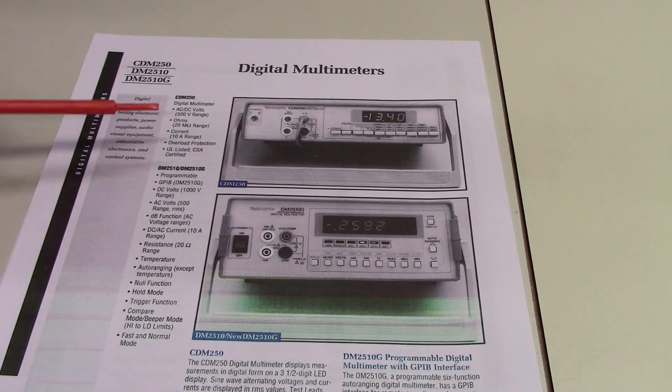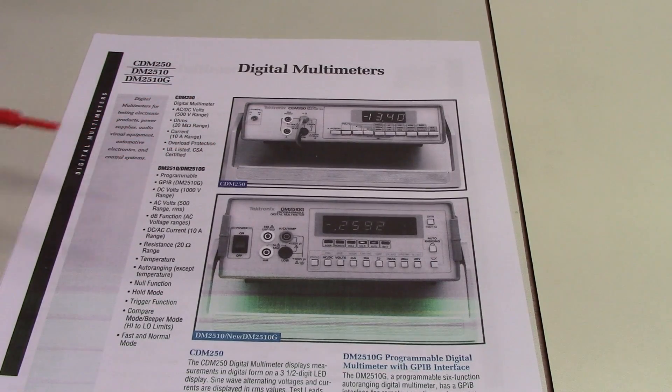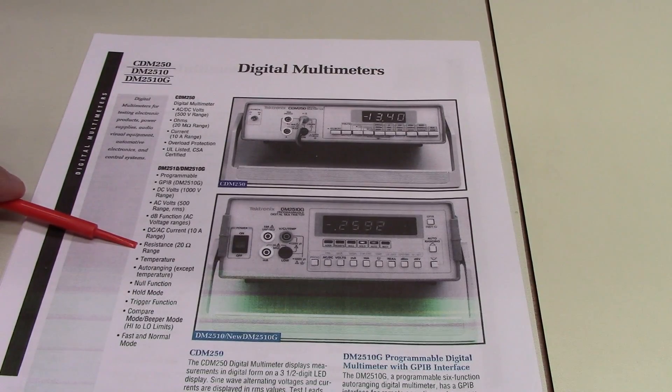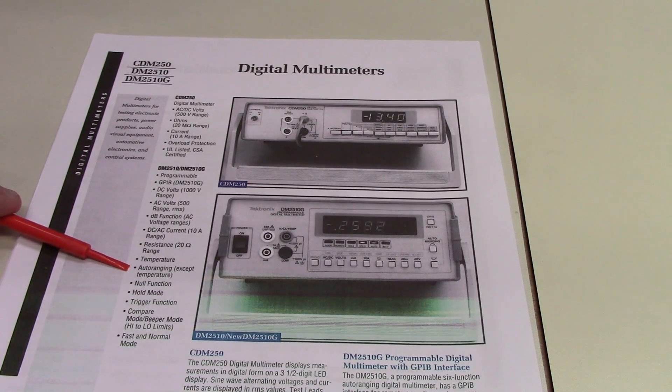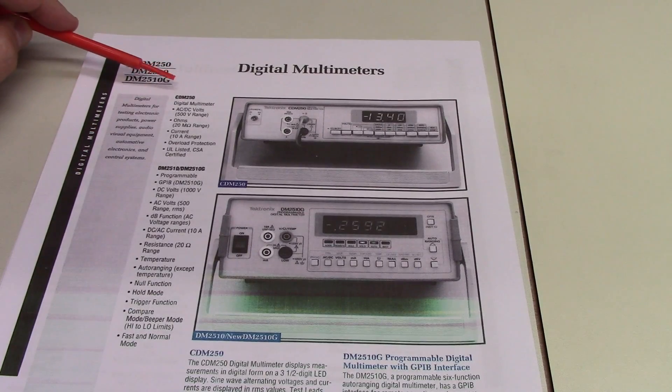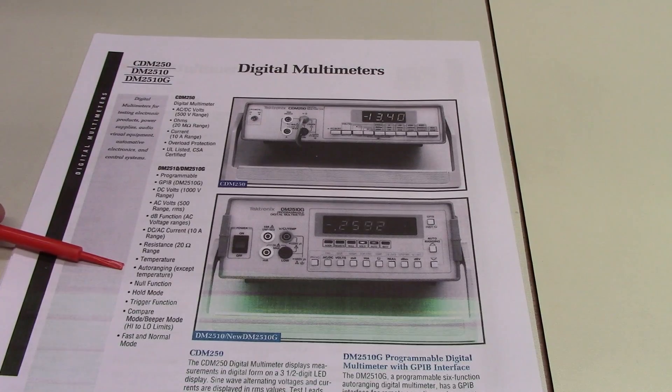This is a programmable multimeter. It's got a GPIB computer interface. It will measure DC up to 1000 volts, AC 500 volts RMS. It will measure AC in dB, does the usual business with current. Not an inspiring range of resistance, up to 20 megaohms, but perfectly adequate. And the nice thing about this is that it's auto-ranging. Unlike the CDM250, this will auto-range on all of its functions except for temperature.